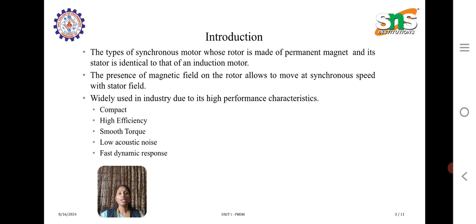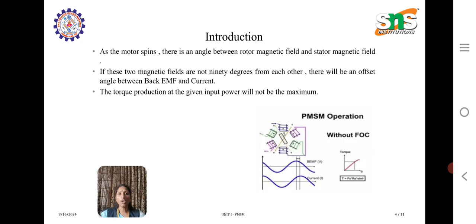Here is a picture showing the angle, the stator position, and the output waveform. As the motor spins, there is an angle between the rotor magnetic field and the stator magnetic field. If these two magnetic fields are not 90 degrees from each other, there will be an offset angle between the back EMF and the current, and the torque production at the given input power will not be maximum in the permanent magnet synchronous machine.